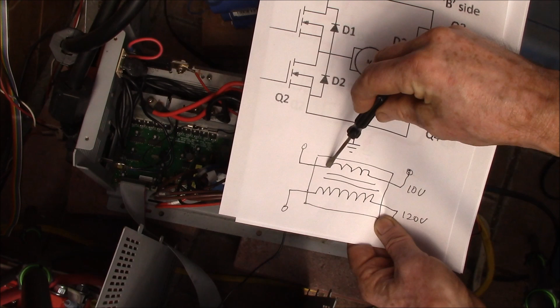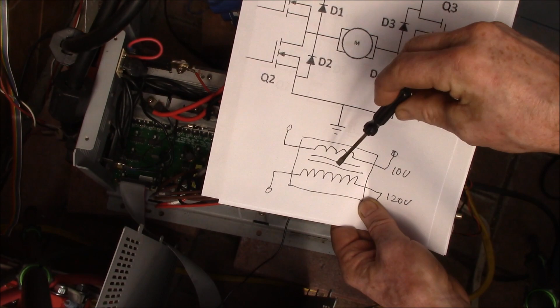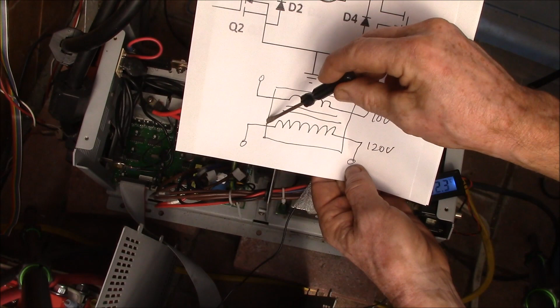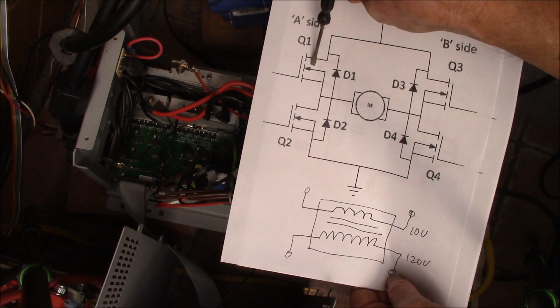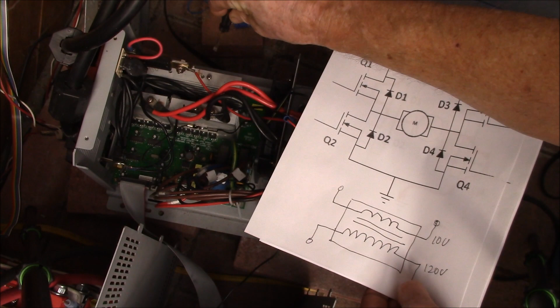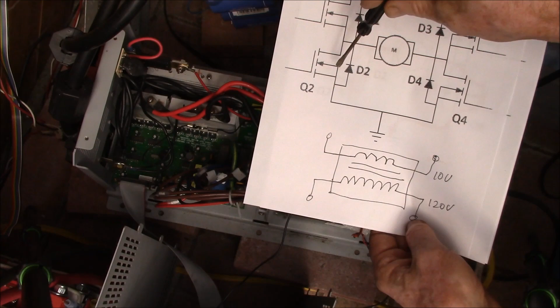So you've got a transformer with a low voltage, approximately 10 volt winding here, and the output of this transformer is a 120 volt output. Here's your H bridge, here's the battery side, there's your battery connection, and there are 5 MOSFETs here and 5 MOSFETs here in parallel, so you've got a total of 10 on that upper heat sink, and then there's the 2 lower heat sinks that are separated here.